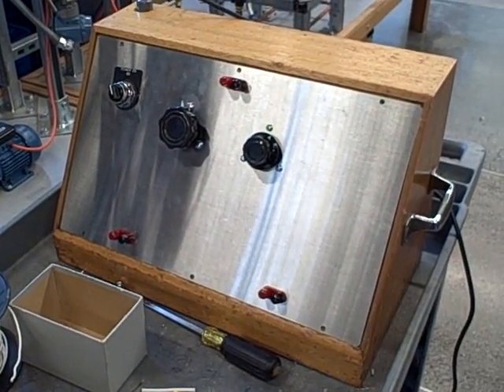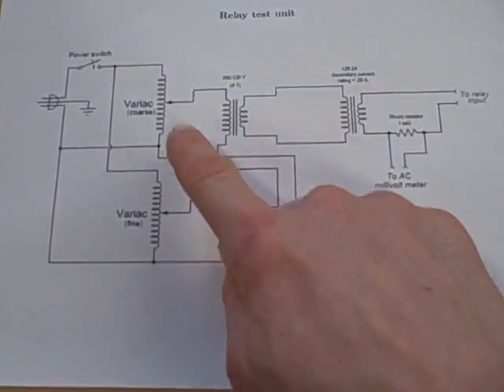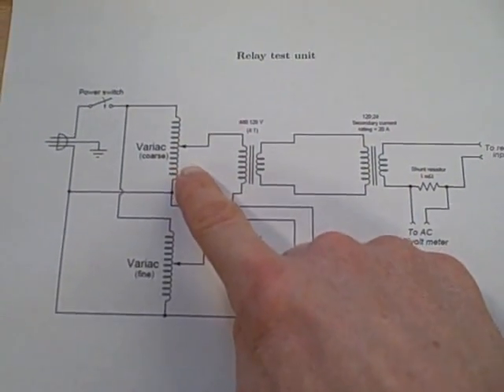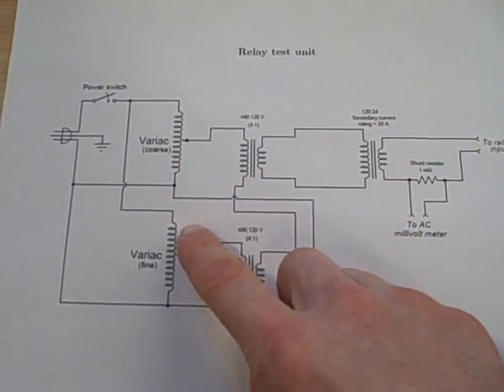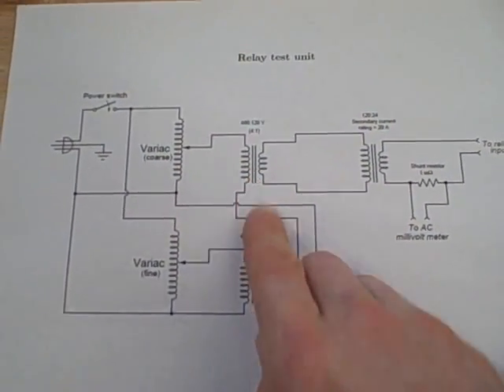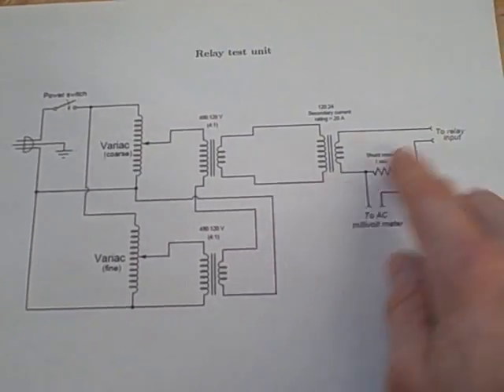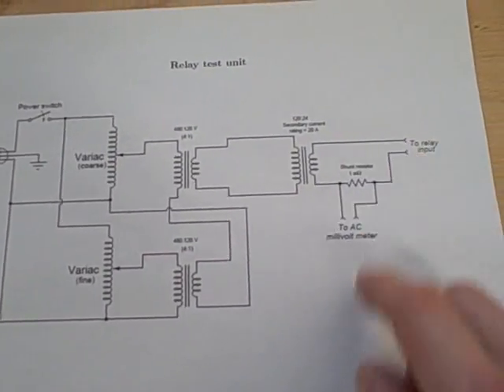So this is the beginnings of our test set. It's based on a couple of variacs, which are variable auto transformers feeding into some fixed ratio transformers to give us a variable amount of current.